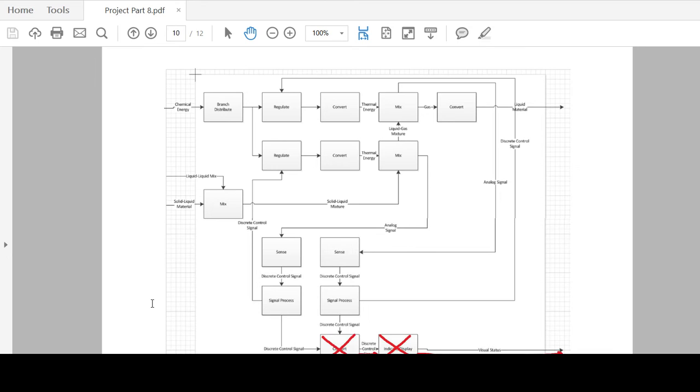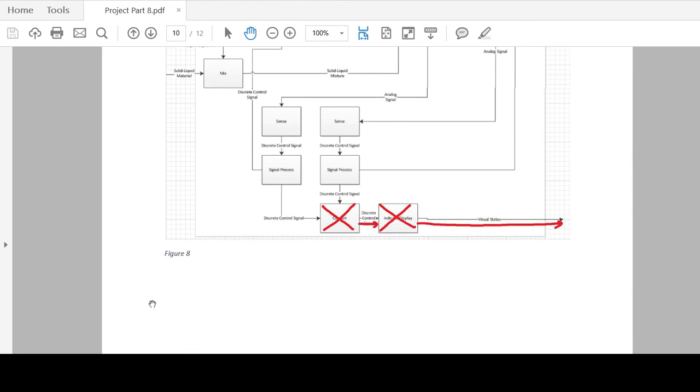First, I looked at the failure of a conversion from the discrete control signal to a display that can be visually read. Essentially, this means that the engineer doesn't get any data. They shut down the entire system of the laboratory to look at the incinerators. This means data and work lost, but it doesn't violate the effectiveness of the entire system as a whole because no microbes escape.